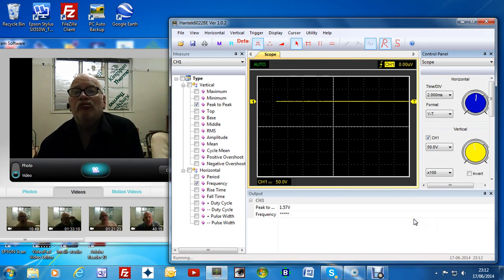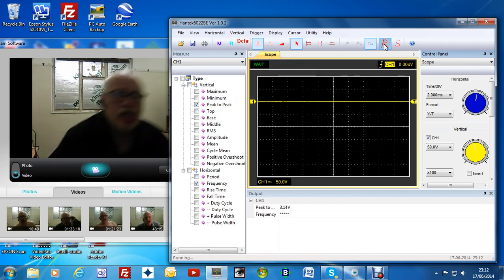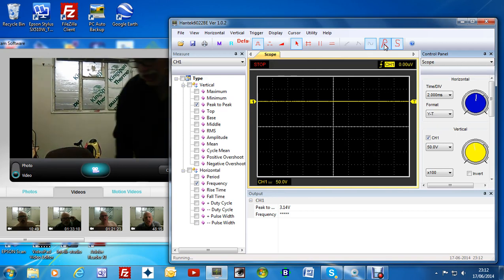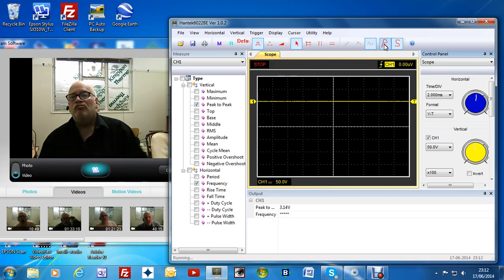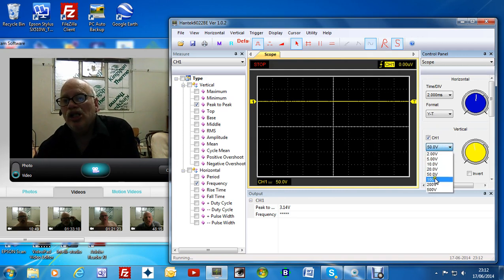Let's put it on trigger. The sweep is single sweep, and you have to reset. I might have to reduce the sensitivity for this. Let's go. Set it off before it triggers again. As soon as I move it triggers. There's actually something in there, so it has to be less sensitive. Put it to 100 volts. And reset.